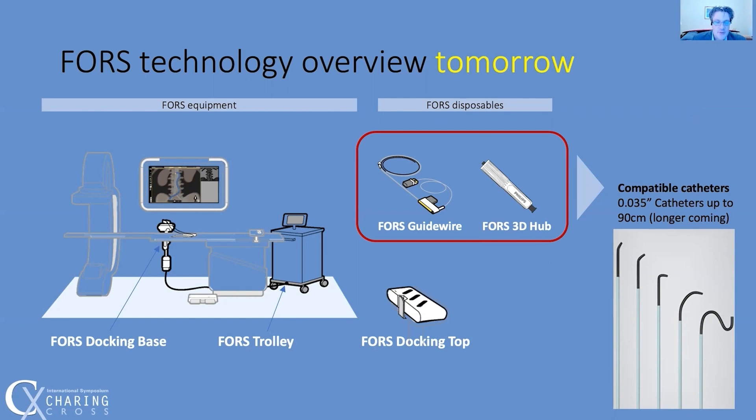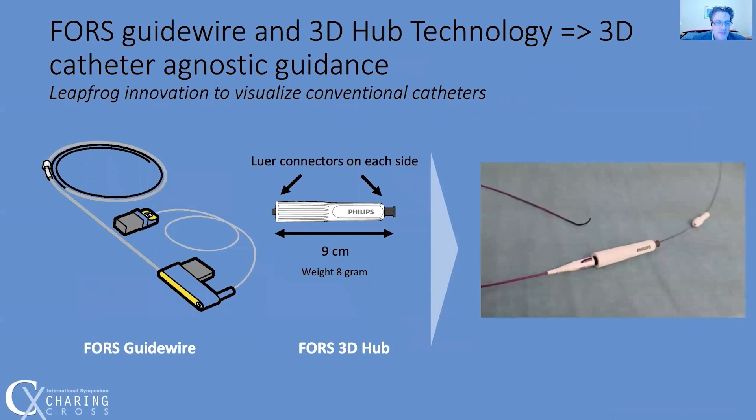This allows the user to employ their catheter of choice, which may include several catheters depending on the anatomy and the device type. The FORS 3D hub, shown in the center, is attached to the catheter and the FORS guide wire is introduced, then the catheter is registered. Each catheter has a specific length, which is confirmed by pushing the wire to the tip of the catheter for registration. The FORS 3D hub knows its position on the wire, so the distance to the tip of the catheter is now known, and it knows that it must follow the position of the wire.